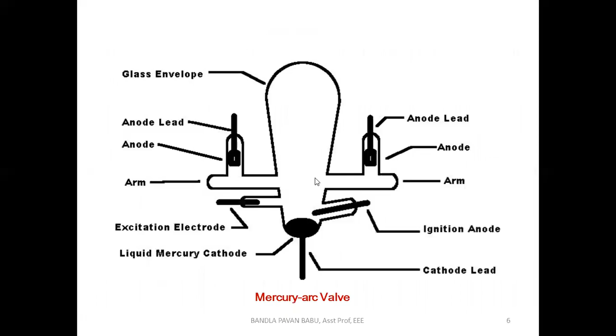Next, the current in the forward conducting valve during this condition reaches typically peak values of 10 per unit. So if the backfire is arising, the switch which is conducting properly under healthy operation, performing a proper action in the forward current direction, gives the constant DC current we require. But if the backfire arises, that current may exceed up to 10 per unit. One per unit is our reference value. Suppose it is 10 amps, then it reaches 10 times that magnitude. So that means a huge amount of current rises there.